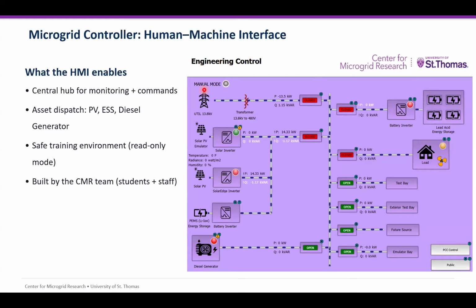As you can see from the screenshot I took from the HMI, we have the grid, which is Xcel Energy in this case, and we have the step-down transformer, and then a breaker, the same breaker we have in the basement shown in the previous picture. We have the point of connection or point of coupling, and here solar panels connected to a solar inverter, plus more solar panels, the energy storage, the diesel generators, the lead acid batteries, the load bank, and these are the test bays, which will be our future resources.